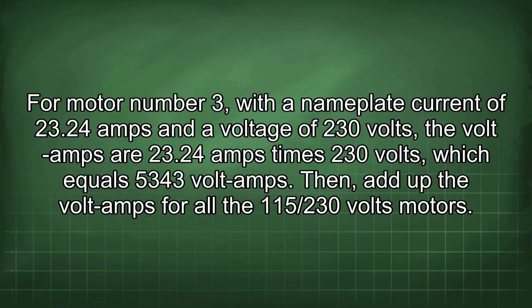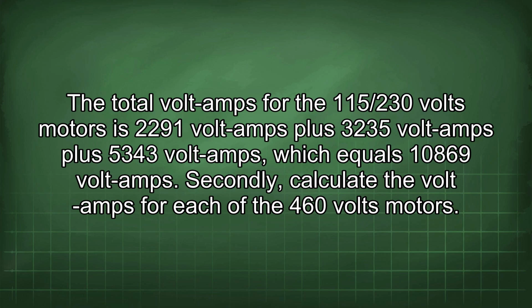3235 volt amps. For motor number 3, with a nameplate current of 23.24 amps and a voltage of 230 volts, the volt amps are 23.24 amps times 230 volts, which equals 5343 volt amps. Then, add up the volt amps for all the 115/230 volts motors. The total volt amps for the 115/230 volts motors is 2291 volt amps plus 3235 volt amps plus 5343 volt amps, which equals 10,869 volt amps.